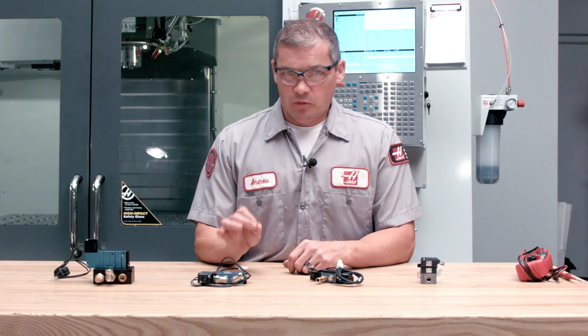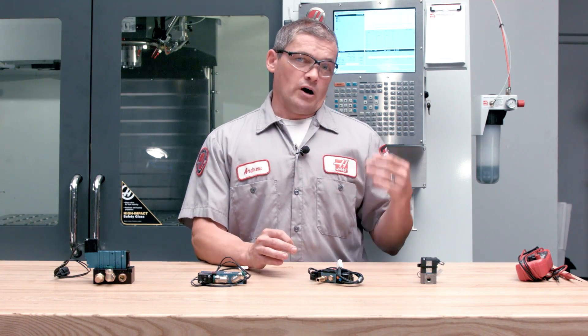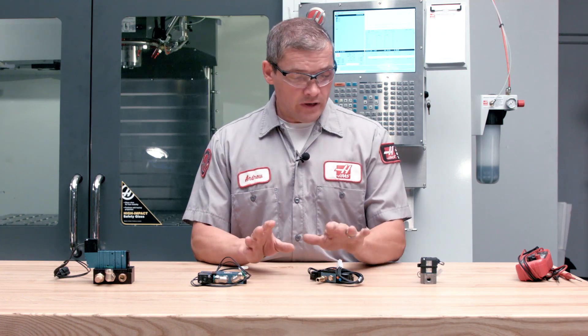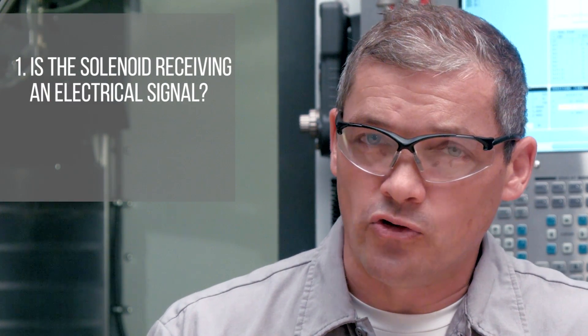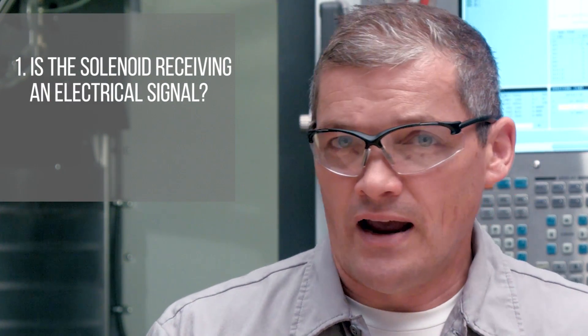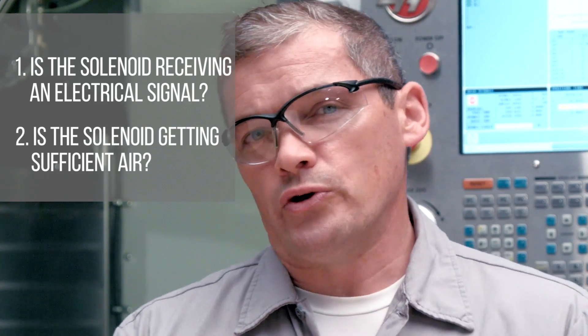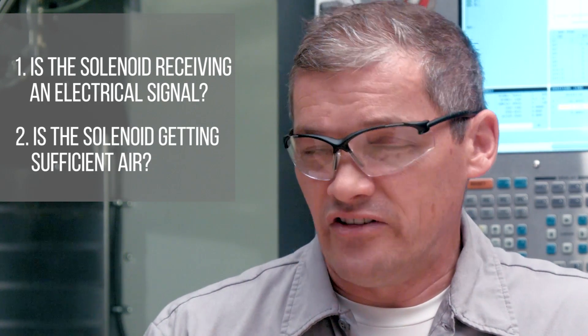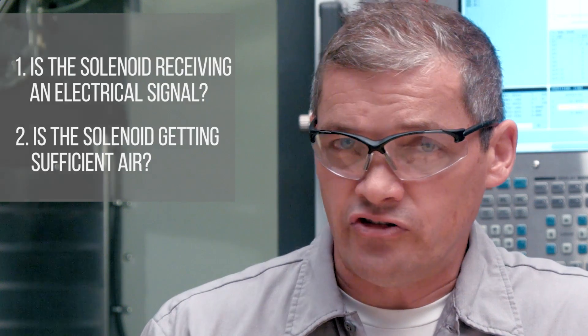None of them want to be hooked up to a contaminated air source. Now that's a very important topic and we're going to get back to that in a minute, but first of all we need to decide if our problem on our machine is the solenoid or it's actually the system that's powering the solenoid. Generally speaking there are two questions you have to ask yourself before you decide if the solenoid is at fault.